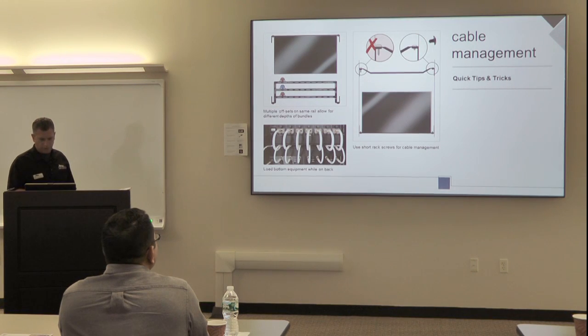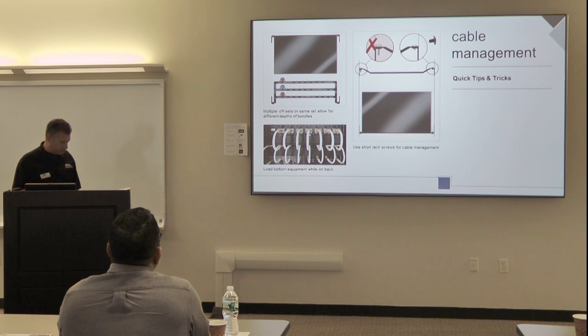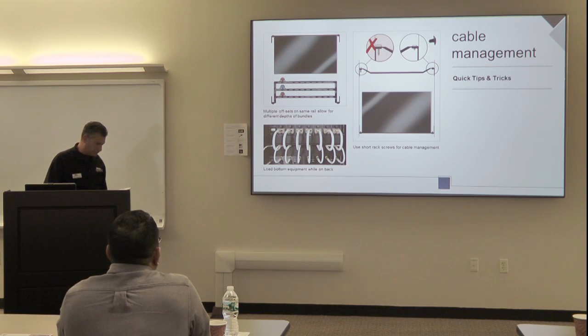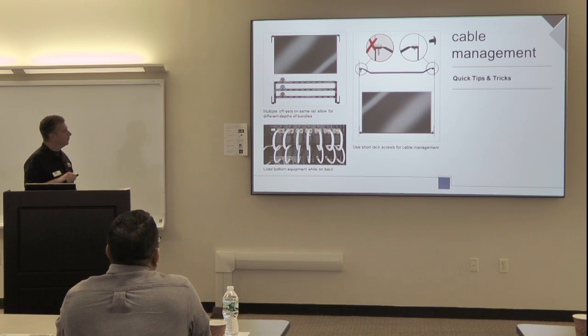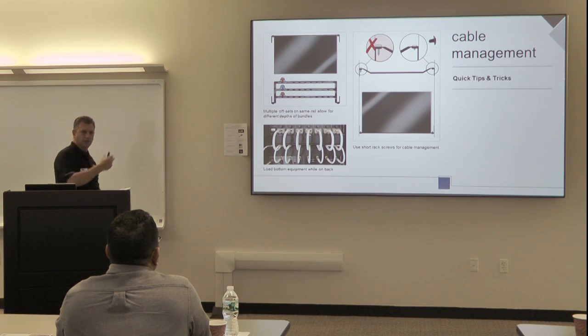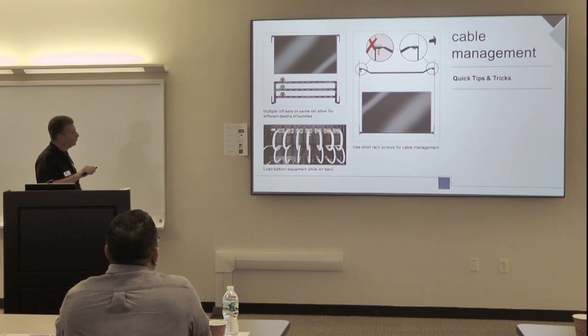So a couple quick tips. One thing we talked about was the rear rail - racks are getting deeper, so sometimes you may have room in the back of the equipment for cabling, but not on the sides. Here you see 3 different offset lacer bars mounted right underneath each other. Looking down at it, this gives you 3 planes of cabling from front to rear instead of trying to go on the side if you don't have the room.